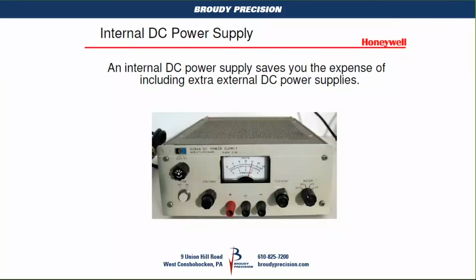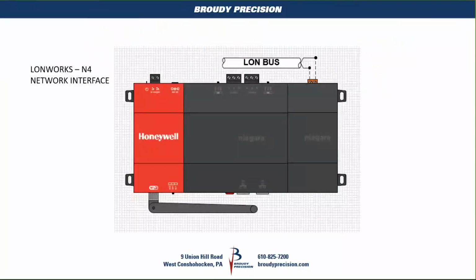For those jobs getting full-blown networks, we put them on JACEs. This is the Honeywell JACE with a LON expansion module to the right. That's for a network job where you have multiple controllers daisy-chained or connected through some topology back to a JACE, and you'd download through your JACE network interface. That interface shows up as a LON card expansion module plugged in on the right here.